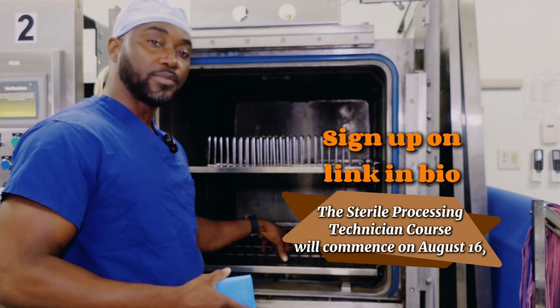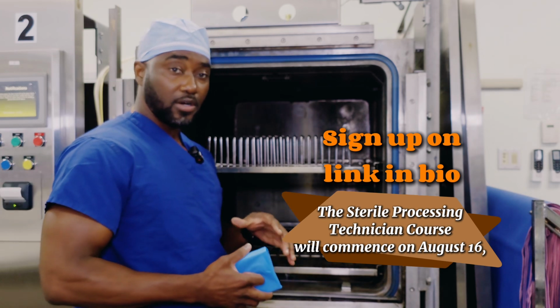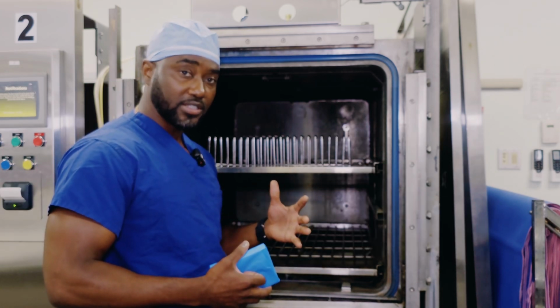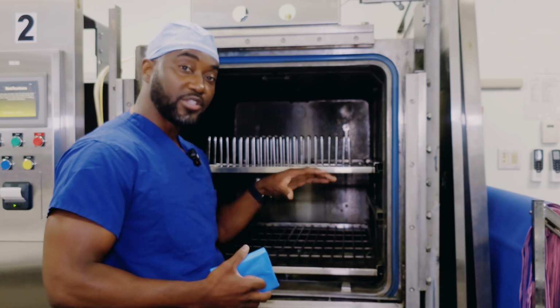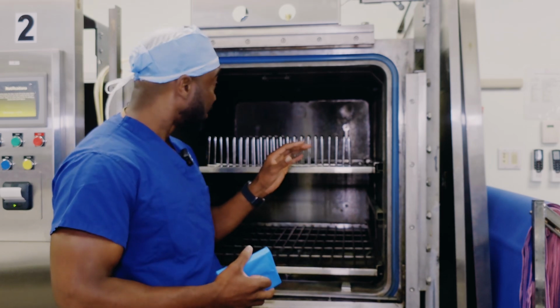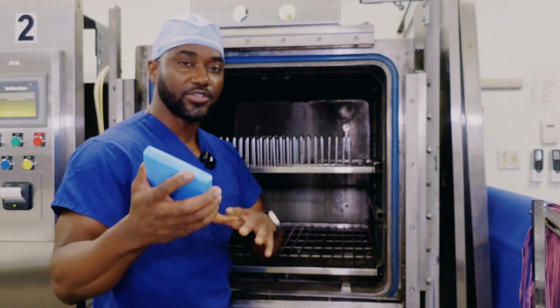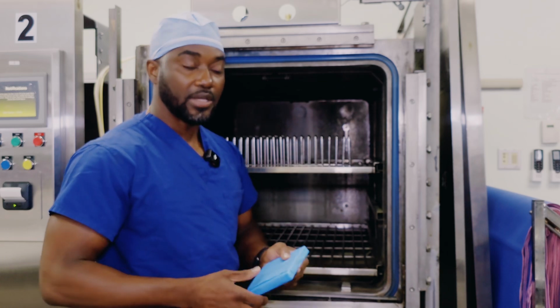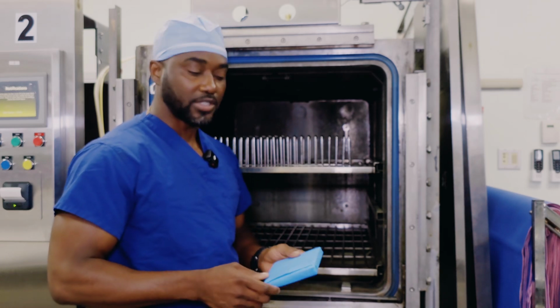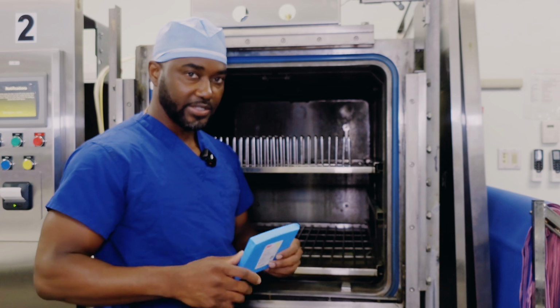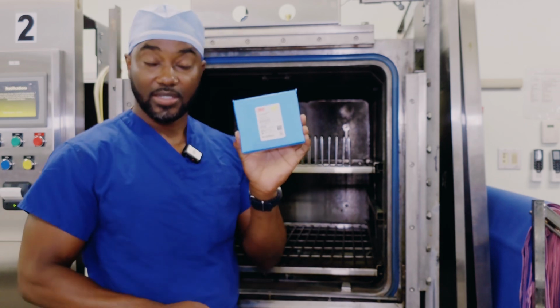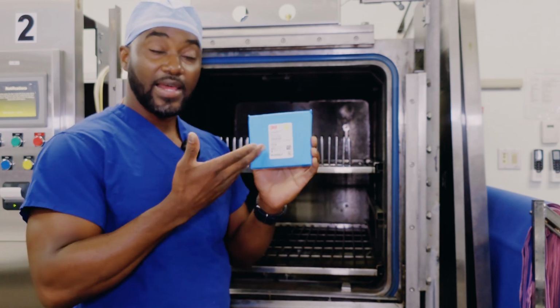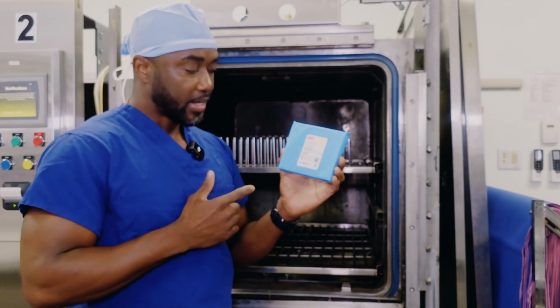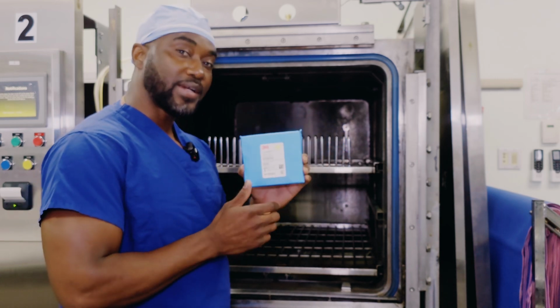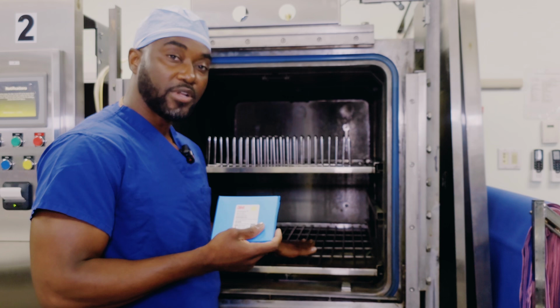Over here that you don't see clearly is a drain strainer. During the conditioning phase of the sterilization process, it sucks out air from this chamber, leaving a vacuum in here. Before that time of sterilization, before the conditioning phase and steam contact with the instruments happens, we have to run a Bowie-Dick test. This is what a Bowie-Dick test looks like. This is a class 2 chemical indicator.